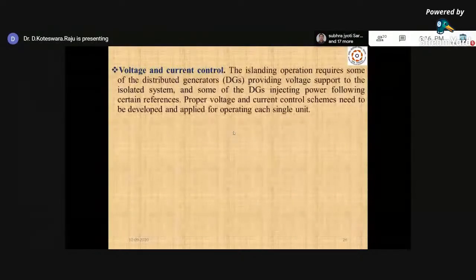First, we will see voltage and current control, which is one of the challenges in microgrids. Islanding operation requires some distributed generators to provide voltage support to the isolated system, and some DGs to inject power following certain references. This means proper voltage and current control schemes need to be developed and applied for operating each single unit.